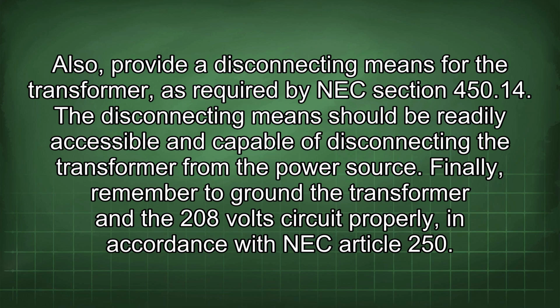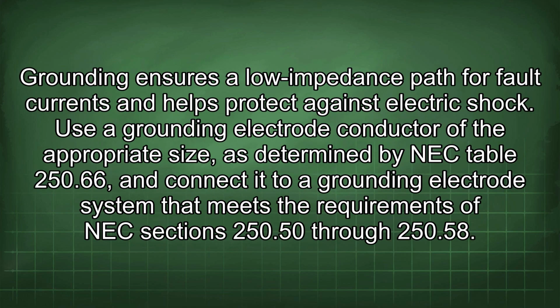Finally, remember to ground the transformer and the 208 volt circuit properly, in accordance with NEC Article 250. Grounding ensures a low impedance path for fault currents and helps protect against electric shock. Use a grounding electrode conductor of the appropriate size, as determined by NEC Table 250.66, and connect it to a grounding electrode system that meets the requirements of NEC Sections 250.50 through 250.58.